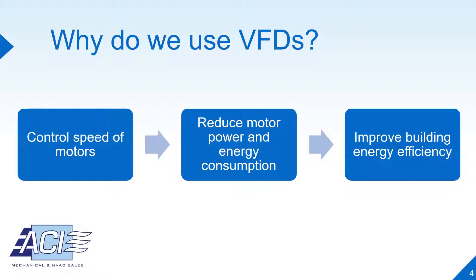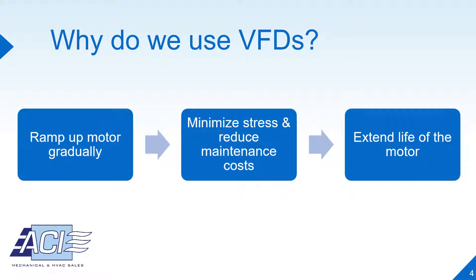By having the ability to modulate the speed of one or more motors based on the system load requirements and operation schedule, VFDs can lead to a dramatic reduction in motor power and energy consumption, therefore improving building energy efficiency. Another benefit to using a VFD is that the drive can be programmed to ramp up the motor to operating speed more gradually, which minimizes mechanical stress, reduces maintenance costs, and extends the life of the motor.